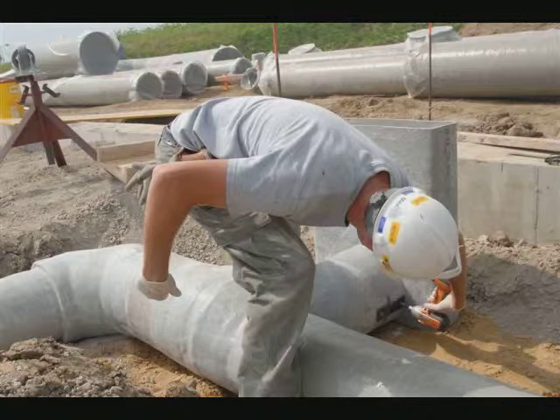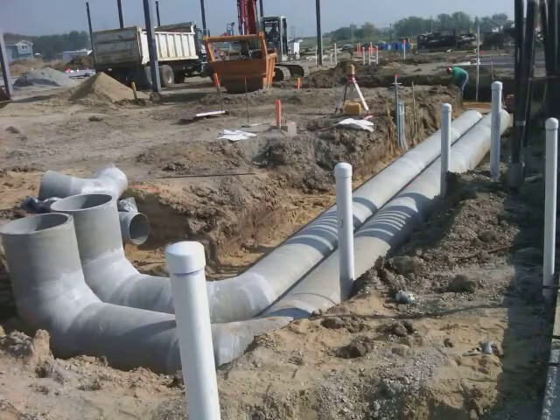Were you responsible for connecting the HVAC equipment to the FRP duct? Yes. Okay. Could you describe how that was accomplished, using a hard connection or flex, or where the transition between fiberglass and metal took place? Yes, where the FRP stubbed up into the mechanical rooms, we had to have fire dampers in the floor, and we just made a transition from sheet metal to the FRP and put the fire dampers on them, and from there we ran sheet metal to the equipment.